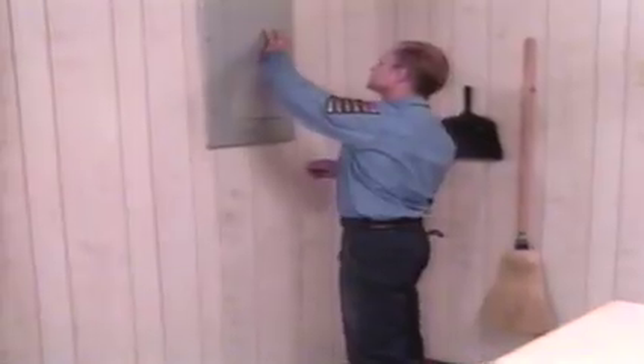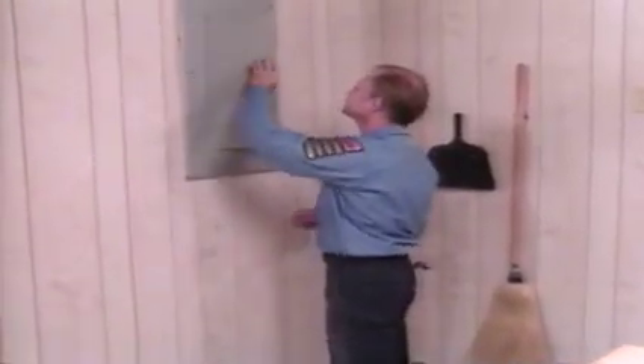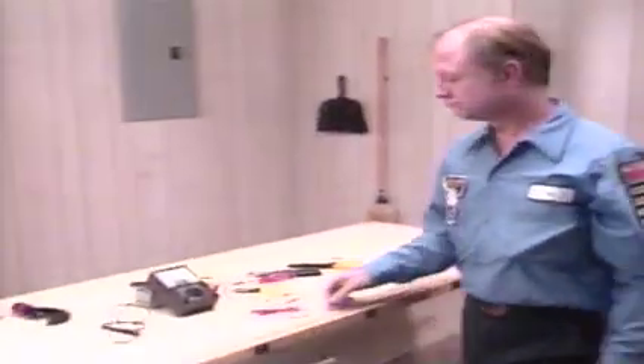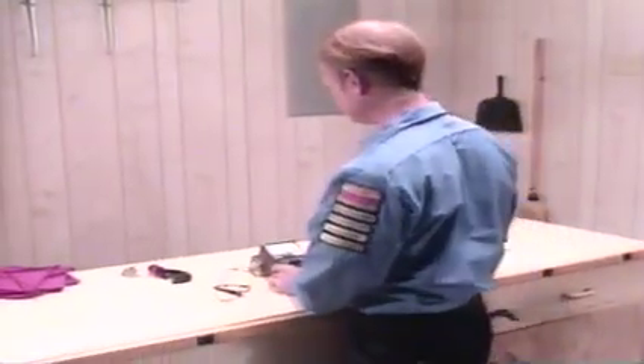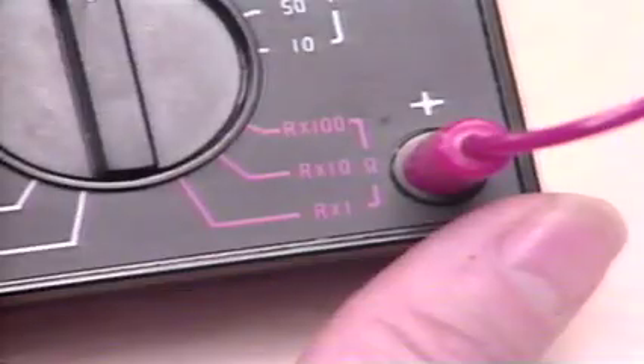Notice on this meter that the top scale is for measuring ohms. You can test for resistance or continuity. The first thing you must do in performing an ohms test is to completely disconnect all the power from whatever is being tested. Now, set the selector switch on the meter to one of the ohms positions.